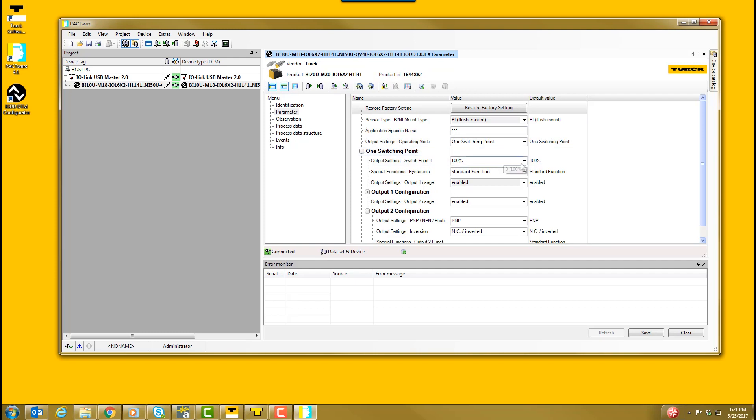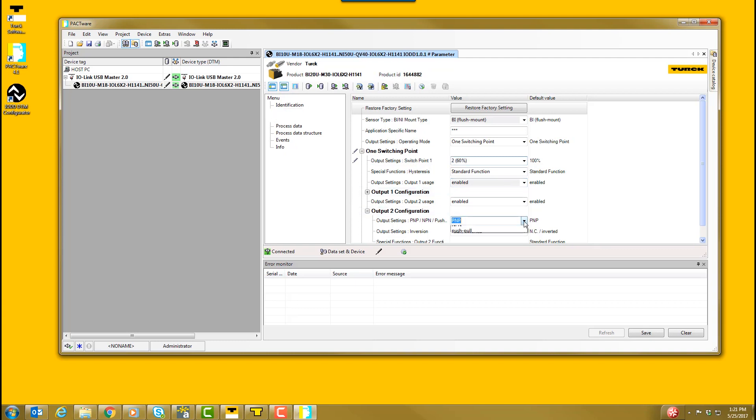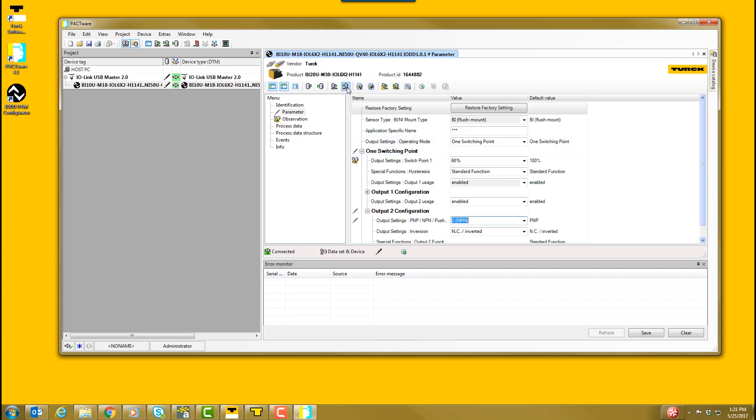In this example, we will change the sensor to have a 60% of the rated operating distance and an NPN switching output. To store the sensor configuration into the device, select Write to Device.